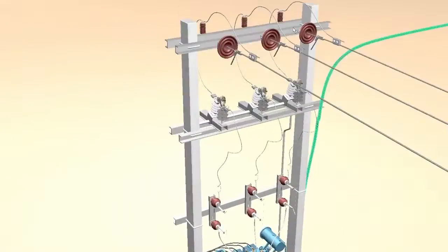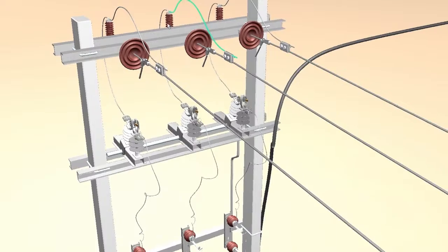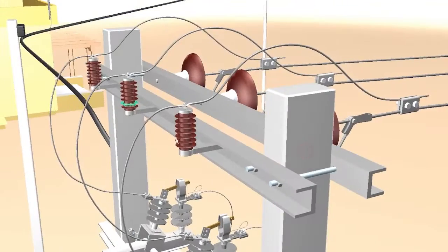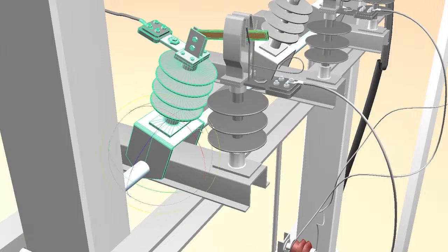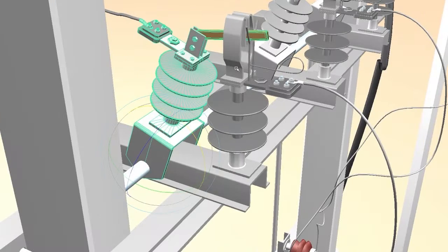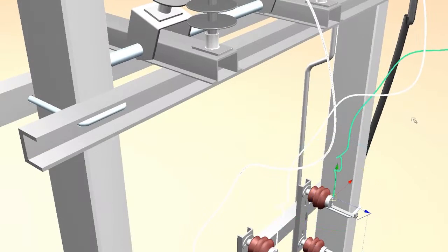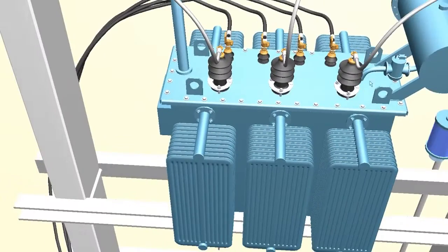From 33,000 volts, it is first connected through the surge arrestor. Then it is passed to the AB switch — here you can see the AB switch and how it works: disconnect, connect, disconnect, connect. Then the wires go to the transformer in three phases, and finally the three phases connect to the transformer through the fuse.